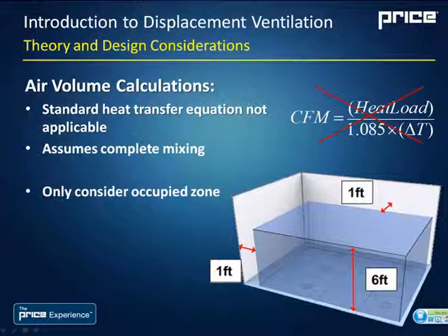So why doesn't the standard heat transfer equation apply? The standard heat transfer equation in its simplest form is just your air volume required is equal to the amount of heat you have in the room divided by the difference in temperature between the room temperature you intend to maintain and the supply temperature that you intend to supply. So in the standard mixed system, you would see your heat load divided by 20 because you see a 55 degree supply temperature and around a 75 degree room temperature. If we were to redo these calculations with a 65 degree temperature, you would see your air volume double, which is not quite correct because, again, this equation only applies to a completely mixed room. And in displacement ventilation, we're only considering the occupied zone, which is that lower 6-foot zone.